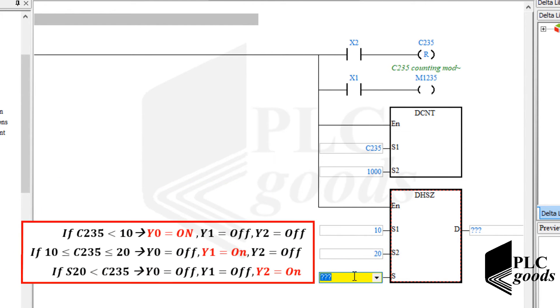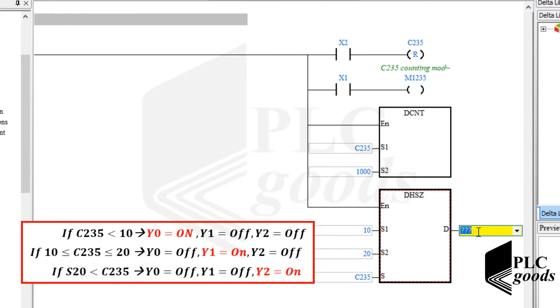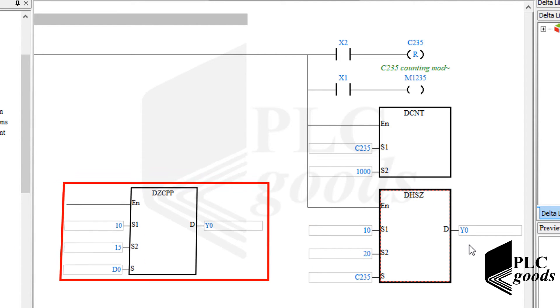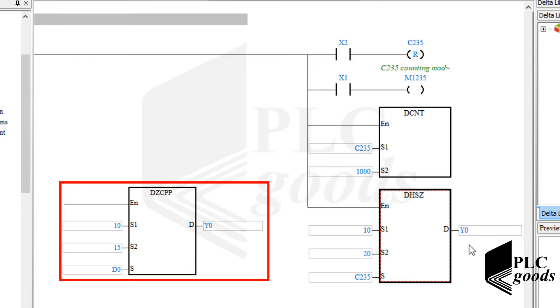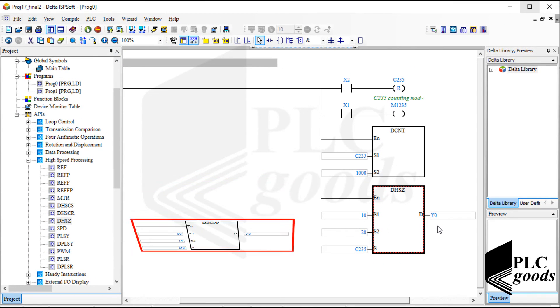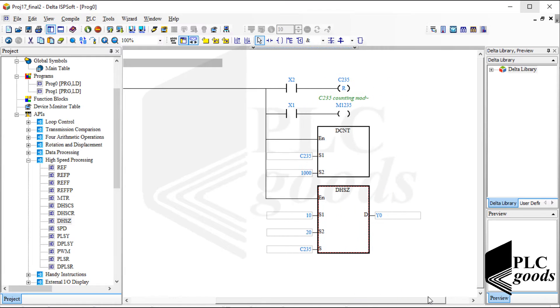The DHSZ instruction works like the DZCP instruction that was explained before. We can also check the counter value with other comparison instructions. The main property of DHSZ is that this instruction updates its outputs independent of the PLC scan cycle. If we use the DZCP instruction instead, the PLC will wait to execute all programs and interrupts to finish the current scan cycle before updating its outputs. Now let me download and test the program.